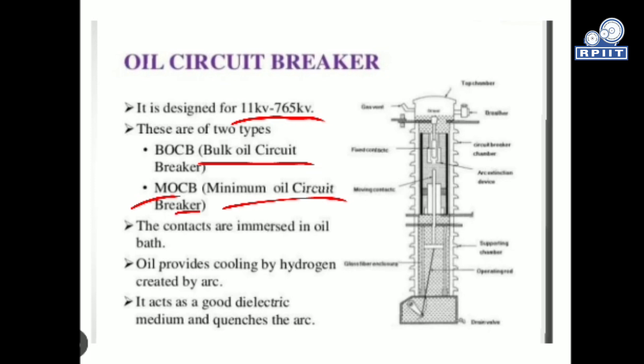In the bulk oil circuit breaker, oil is used in bulk quantity, whereas in the minimum oil circuit breaker, a minimum quantity of oil is used for immersing the contacts. These contacts are immersed in an oil bath. The oil provides cooling by hydrogen created by the arc during arc production whenever the contacts open and close. It also acts as a good dielectric medium and quenches the arc.